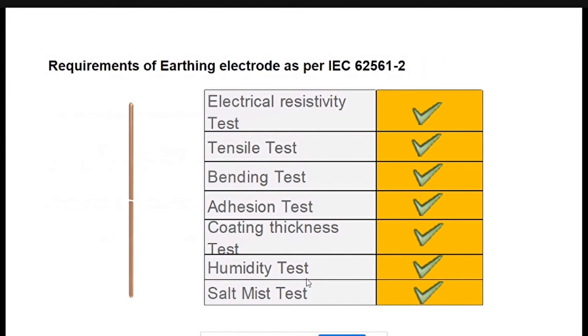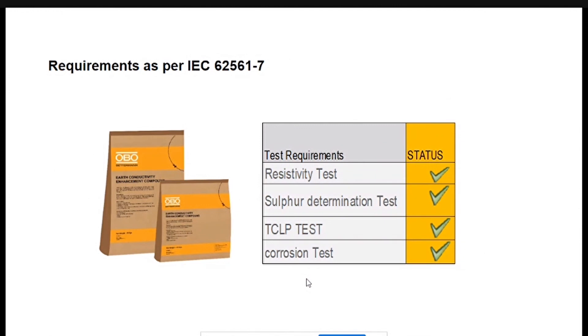When it comes to compound, very importantly any compound can be used provided they have passed the resistivity test, sulfur determination test, TCLP test, and corrosion test. If any one of these is not properly done or if the compound is not sufficient to take the testing, then it is unfit to be provided in the earthing system.